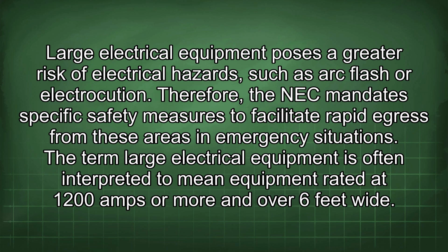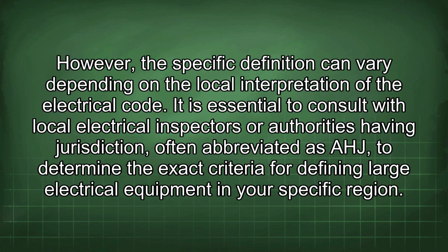The term large electrical equipment is often interpreted to mean equipment rated at 1200 amps or more and over 6 feet wide. However, the specific definition can vary depending on the local interpretation of the electrical code. It is essential to consult with local electrical inspectors or authorities having jurisdiction, often abbreviated as AHJ, to determine the exact criteria for defining large electrical equipment in your specific region.